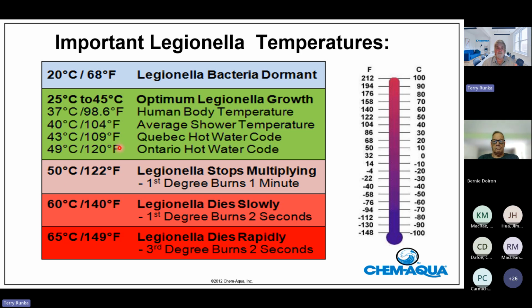The code says you can't have your hot water hotter than 49 degrees C because you'll scald people. But that is in the growth range. And in Quebec, you can't have your water hotter than 43 degrees C. Again, scalding is always going to be a big issue. Now, at 50 degrees C, Legionella stops multiplying. Doesn't die, but stops multiplying. At 60, it begins to die slowly. And at 65, boom, Legionella bacteria dies instantly. However, if we ran all of our cooling towers at 65 degrees, we wouldn't get much cooling and people would get scalded.